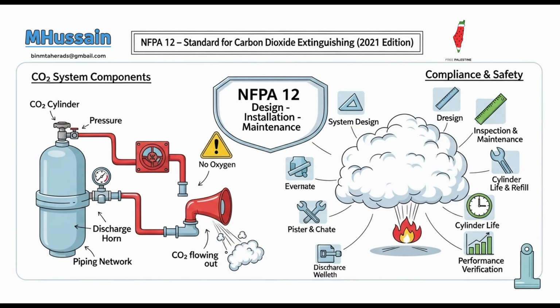Because the mobile supply is primarily considered fire brigade or fire department equipment, its effective use relies heavily on trained personnel who understand its operation and the specific hazards it protects. Trained responders needed. Given that there might be inherent delays in getting the mobile supply to the hazard and making the necessary connections, the standard acknowledges that extra CO2 might be needed to compensate for those deployment times. Need more gas to make up for the setup time. Ensuring the required extinguishing concentration and duration of protection can still be met despite the operational lead time.